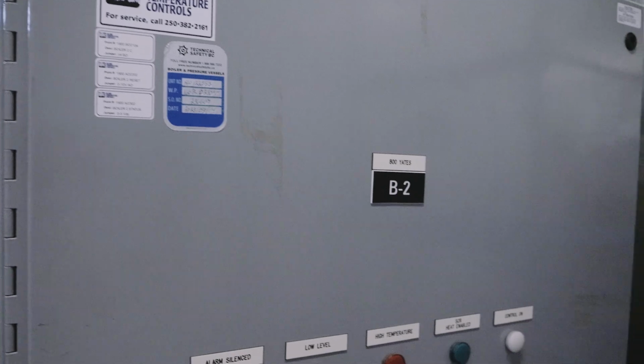SES built it in so that the boilers could actually bump up the temperature from 47, which is what the heat pump likes to provide, up to 52, which is what we really require in the dead of winter. That way we were able to maintain our system temperature without dipping too much into energy costs, and also prolong the life of our heat pump without running it flat out in the winter.